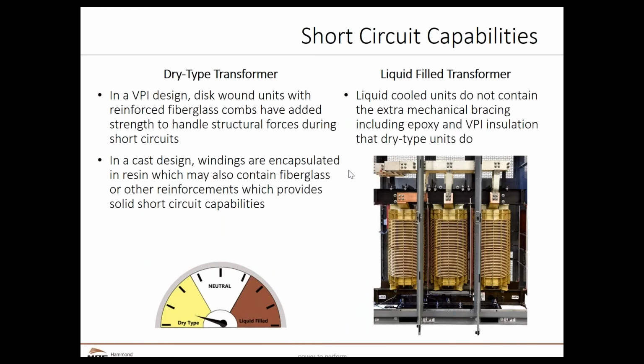We hope not, but all transformers could experience a short circuit event. When a short circuit event occurs, we are hoping that the fuses or circuit breakers, whatever the overload technology is, will clear the fault quickly. However, in between when that fault is cleared and when the overload occurs, the coils will be experiencing huge increases in current. We're not really worried about the heat for that short-term duration, provided that the breakers and fuses are properly set up. However, that current also creates an amazing amount of mechanical forces within those wires, and those wires could deform. They can break, they can cause the coils to fail.